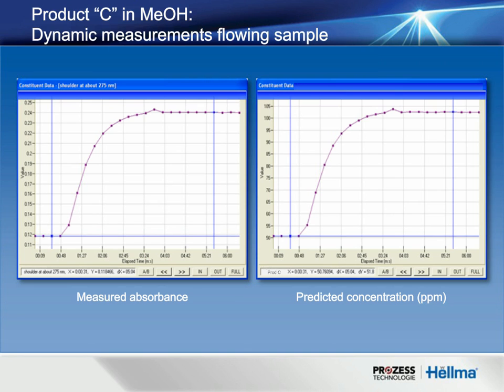Okay. How do you correlate the concentration in the effluent to the residue on the surfaces of the equipment being cleaned? That's tricky. It's difficult. Empirically, as I talked about before, the process of qualifying and validating the UV approach would be multi-step, and I have seen some attempts at correlating the direct UV spectroscopic approach with the swab tests, but this measures what has been picked up in the rinse aid.